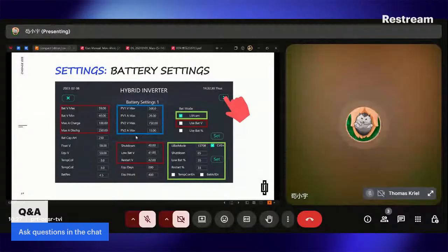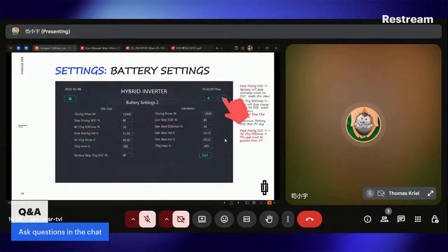And for the PV settings, you can see in the blue box, the default one is like this. And sometimes the solar panel voltage we use is too high or too low. We need to adjust that here. You can click on the value and then input it, then click set, and it will require you to input the setting password. It should be 6 times 8, so it's 888-888. And for old firmwares, it's hard to find it now. But for old firmwares, the password is 750192. But I think in the South African market, basically we are all using the new firmware.